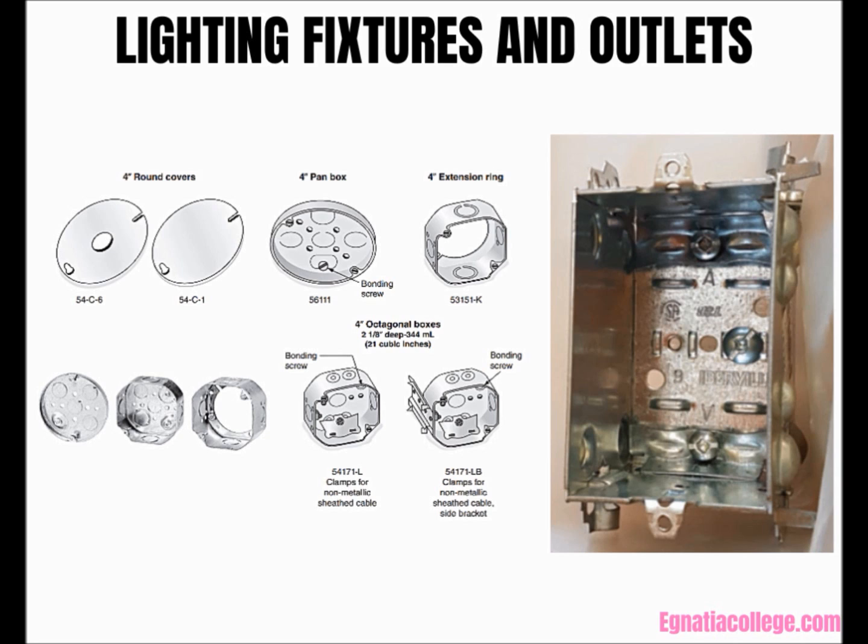Most modern surface mount lighting fixtures can be fastened to an octagon box or an outlet box with a plaster ring using appropriate 8-32 metal screws and mounting strap furnished with the fixture. When mounting an outlet box in a wall or ceiling that is to be insulated and covered with a vapor barrier, you must make special provision to maintain the integrity of the vapor barrier. A polyethylene boot covers the outlet box and is sealed to the 6 mil polyethylene vapor barrier. This figure shows a typical polyethylene boot installed on a 102 mm (4-inch) octagon box.